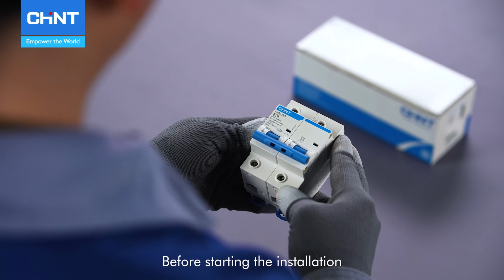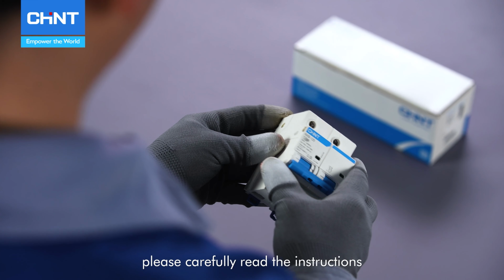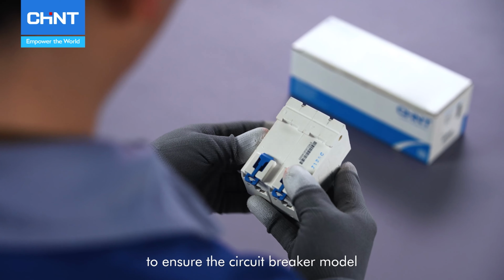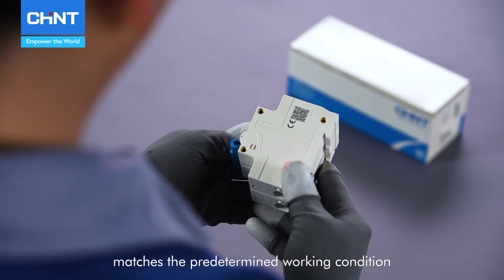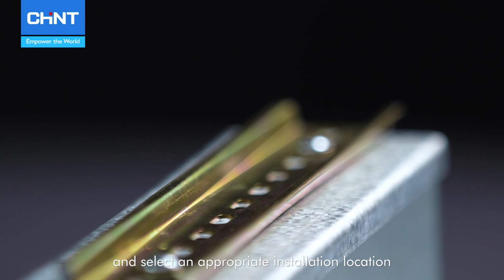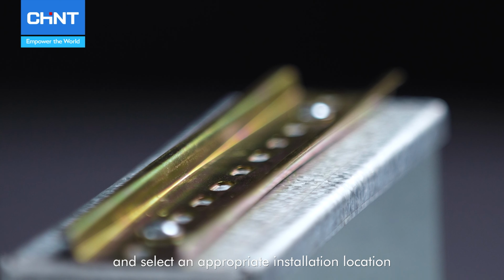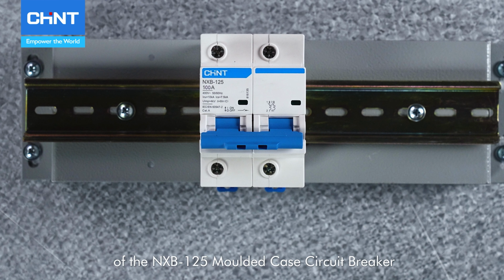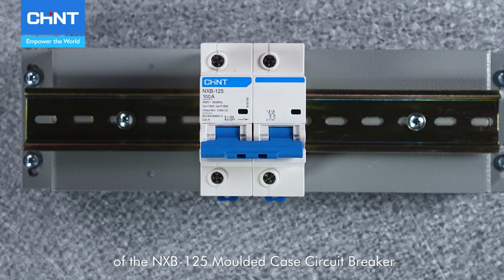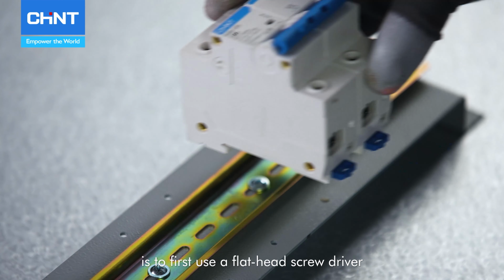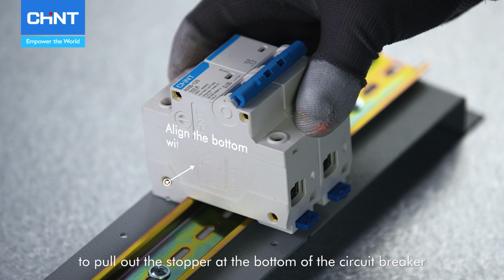Before starting the installation, please carefully read the instructions to ensure the circuit breaker model matches the predetermined working conditions and select an appropriate installation location. The technique for installing the NXB-125 molded case circuit breaker is to first use a flathead screwdriver to pull out the stopper at the bottom of the circuit breaker.